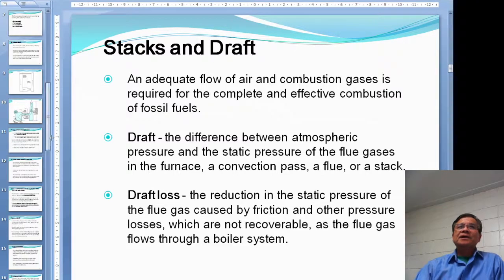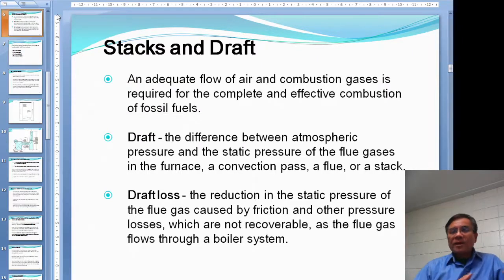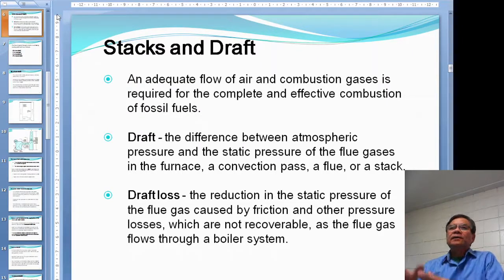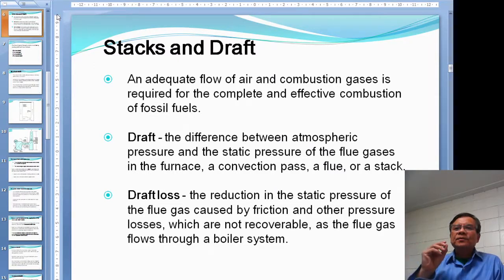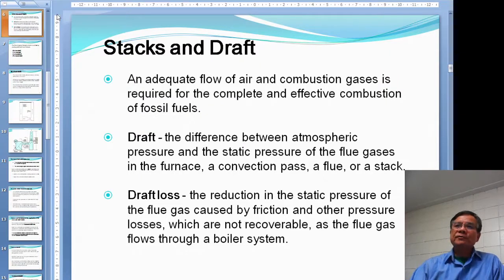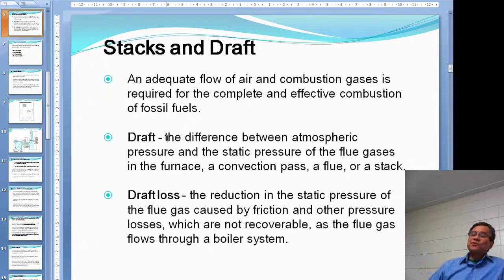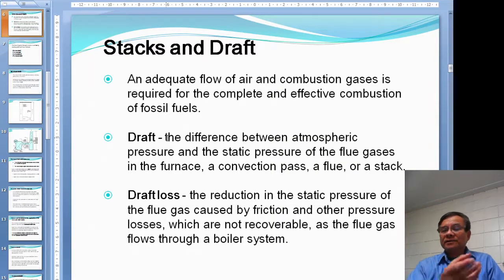For natural draft, we need a stack — at home we call it a chimney. If you want enough combustion, you need full airflow inside the furnace. You need to create a draft — the draft is required to completely burn the fuel. In our case, the draft is the difference between the atmospheric pressure and the static pressure inside the furnace or the chimney.